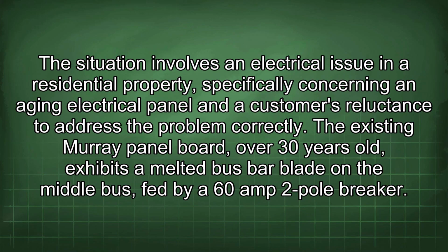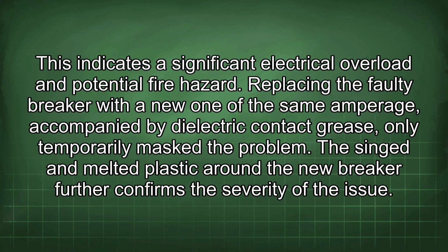The situation involves an electrical issue in a residential property, specifically concerning an aging electrical panel and a customer's reluctance to address the problem correctly. The existing Murray panel board, over 30 years old, exhibits a melted bus bar blade in the middle bus, fed by a 60-amp 2-pole breaker. This indicates a significant electrical overload and potential fire hazard.